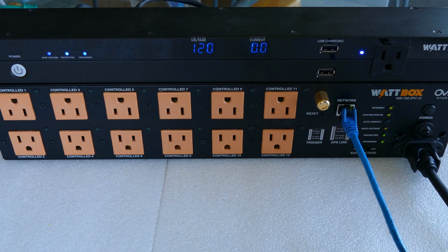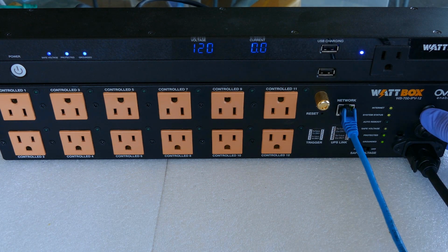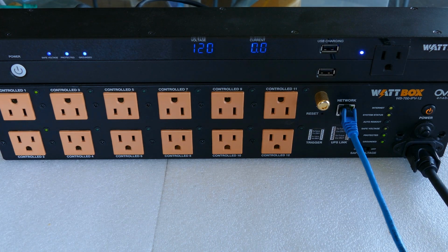Okay, we got a solid green LED for the system status, along with several other LEDs. I'll press the power button. I can hear the outlet relays firing, and the corresponding green LED indicators are illuminating. I think it's fixed. I confirmed all the outlets are working.